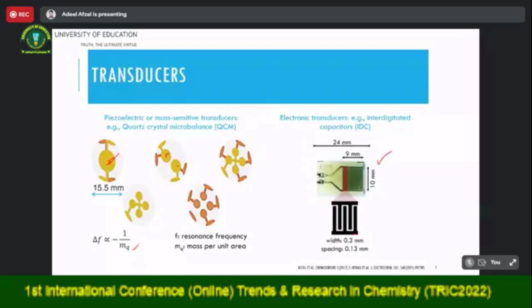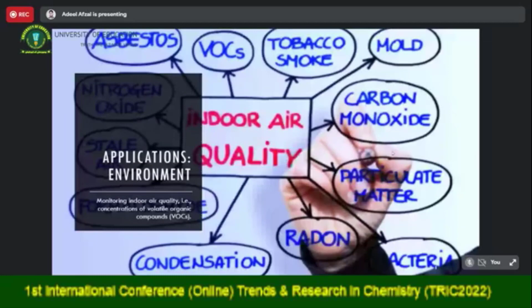Now, the first application related to the environment is an example that we have already performed, and it was the detection of formaldehyde and volatile organic compounds. So I will quickly go to the slide where we have the setup, in which we have a transducer, the sensor device, in a sensing chamber, and here the gases are mixed with the organic vapors. So air, or nitrogen, is mixed with the organic vapors, and these organic vapors are exposed to the QCM device, and the QCM device then detects the organic vapors, and we see a decrease in frequency through this oscillator circuit, and we record this data in the computer.